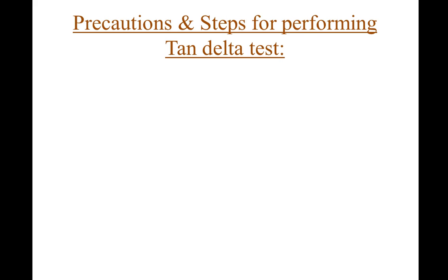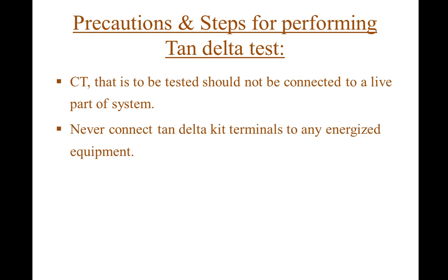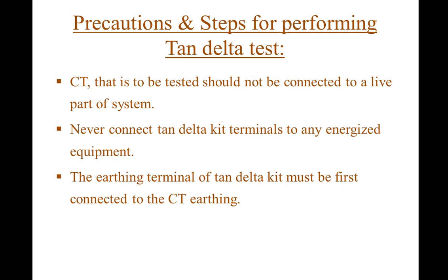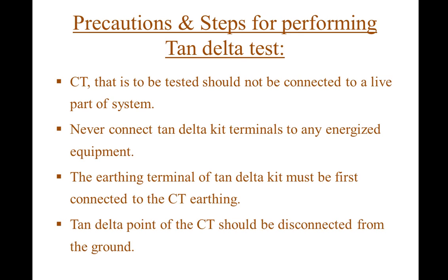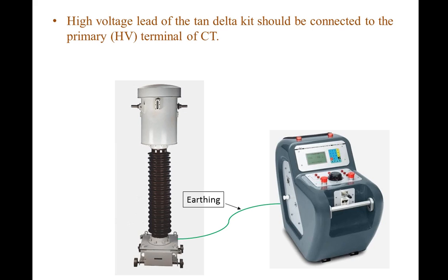Precautions and steps for performing tan delta test: The transformer to be tested should not be connected to any live part of the system. Never connect tan delta kit terminals to any energized equipment. Before doing any connections, the earthing terminal of the tan delta kit must be first connected to the site earthing. As shown in this figure, the earthing connection should be done first.